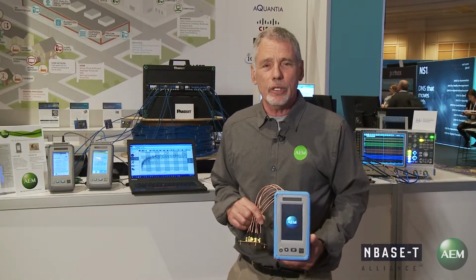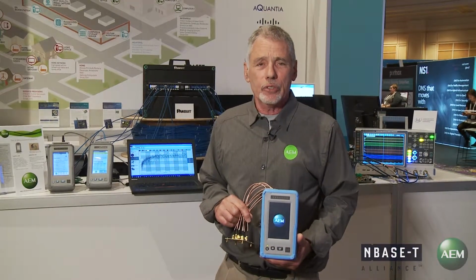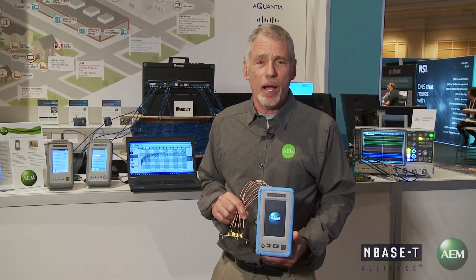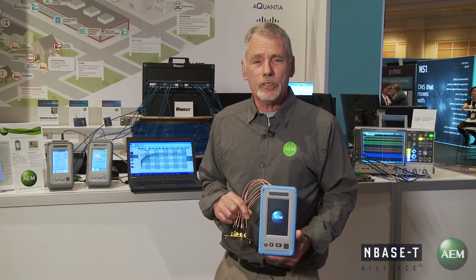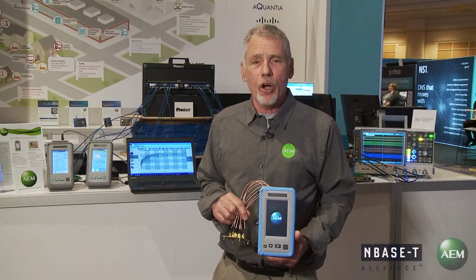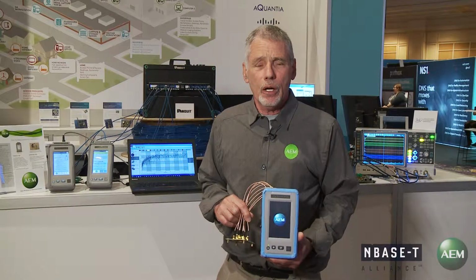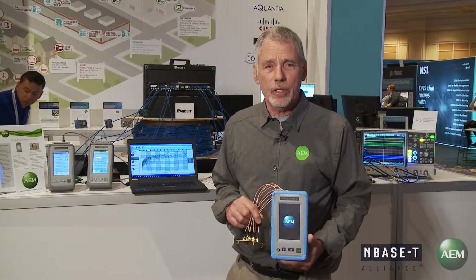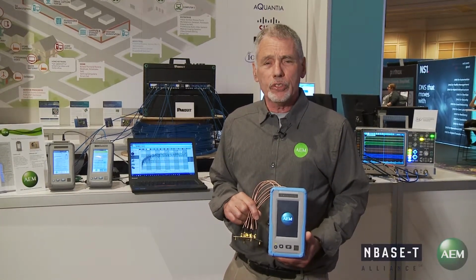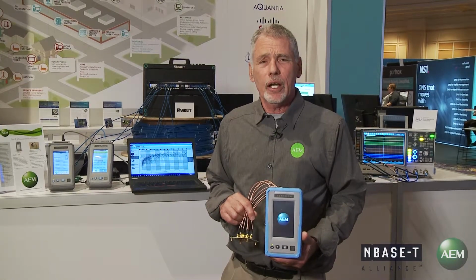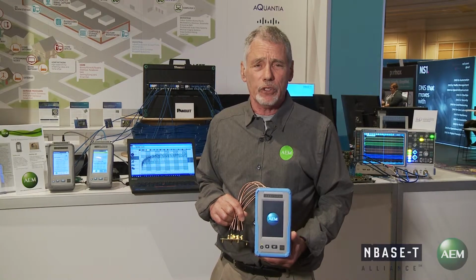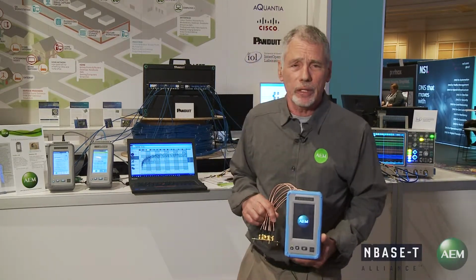In addition to the cabling infrastructure, it makes measurements of active devices like equipments. It can measure the impairments of the connectors on the active devices and is optimized for those bandwidths. It's complemented with a software that enables post-processing information, not just the information for the measurements itself, but you can save each of the measurements and records and post-process that information in terms of the additional impairments and functionalities and comparing it against limit lines.